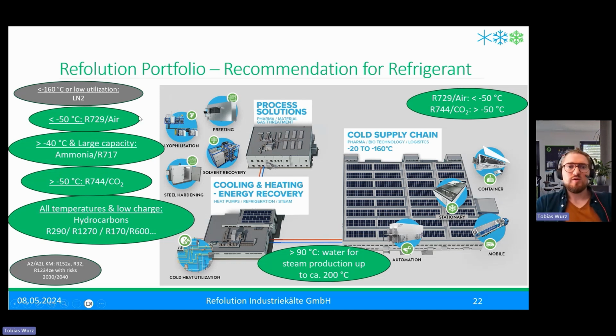So again, air for lower temperatures. We could use ammonia for large capacities. CO2 we can use. So for these low temperatures, even for these ultra low temperatures, we have something to choose from. And for all temperatures, if you have smaller units, small means below 1 megawatt, you can use hydrocarbons without problems in all areas, in all temperature fields, because we have methane as the lowest temperature refrigerant up to isobutane, and the more C's you have, the higher you can go up with the temperature.